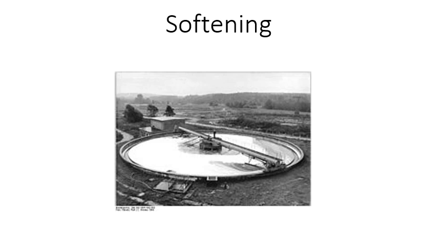Chemical precipitation is also known as lime or soda softening. Hardness is not reduced to 0. The minimum hardness achievable is between 30 and 40 milligrams per liter, which is very expensive. Most plants will target 100 to 150 milligrams per liter. Low hardness finished water equals more lime sludge and higher treatment costs. For 1 ton of lime used, it creates 2 to 3 tons of waste.